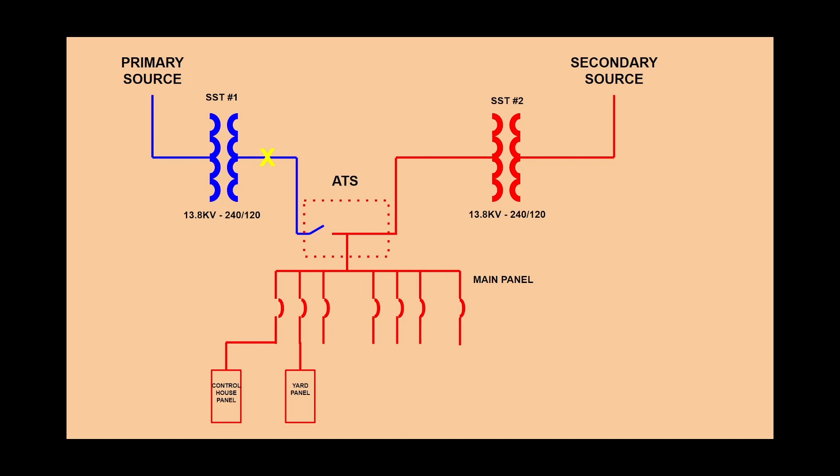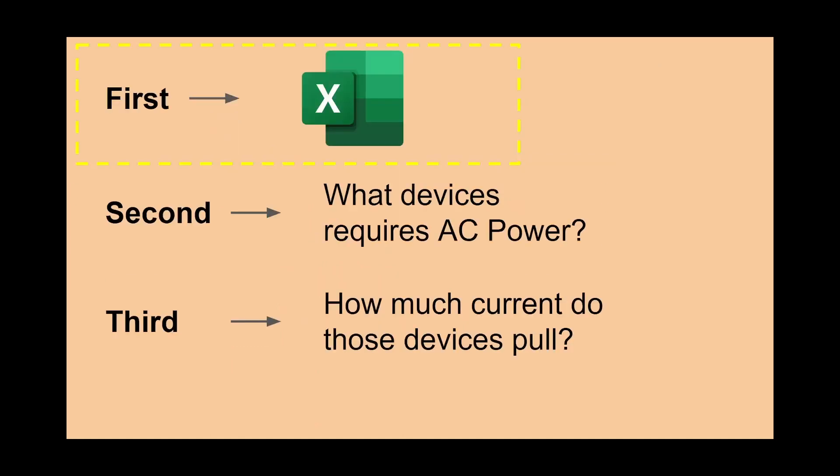So to answer the question what you're going to need to perform the AC Calc. First you're going to need that template spreadsheet. Second you will need to know all devices that need AC power in your substation. Third you will need to know how much current each device pulls. You can find the values of these devices on their manufacturer's websites. Once again more than likely someone has a completed AC Calc that you can refer to as a go by.